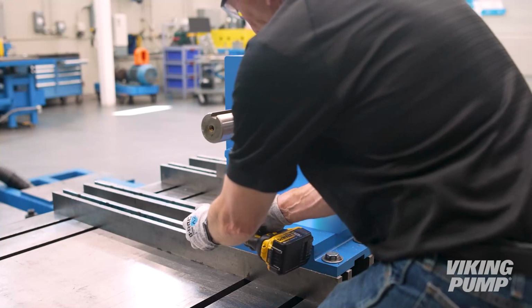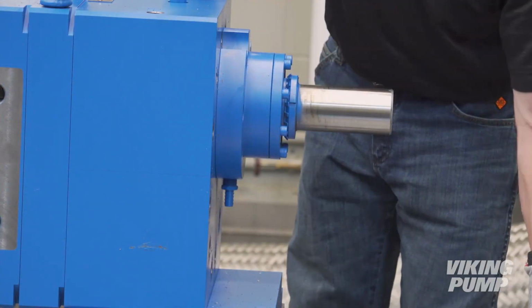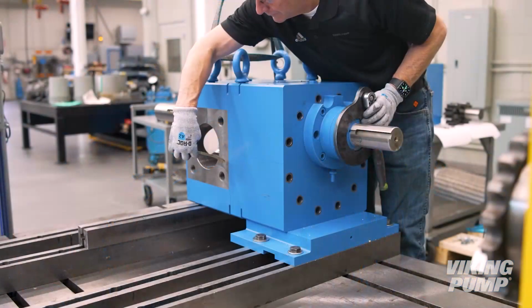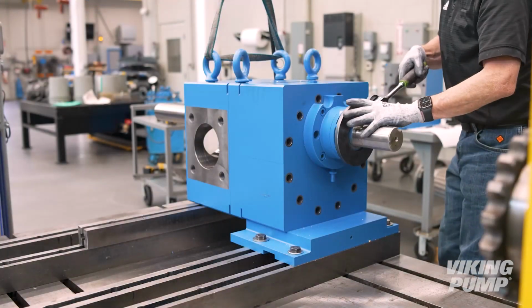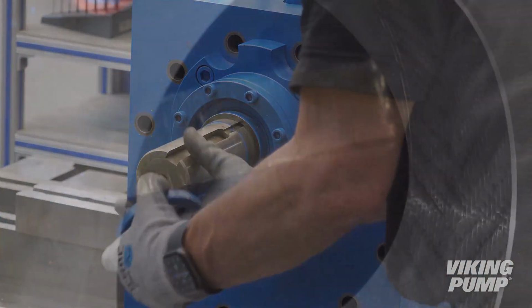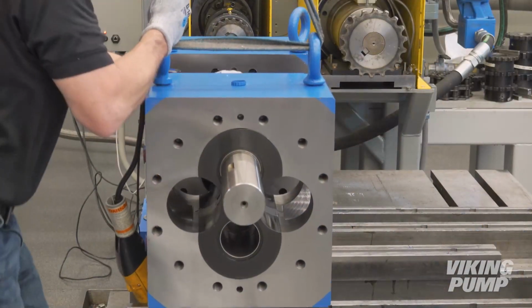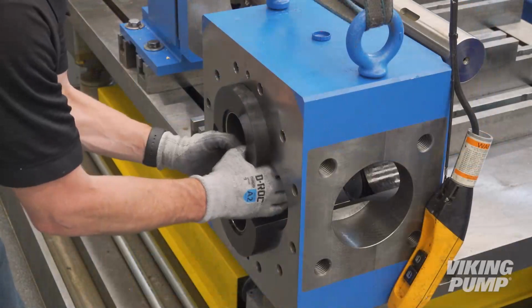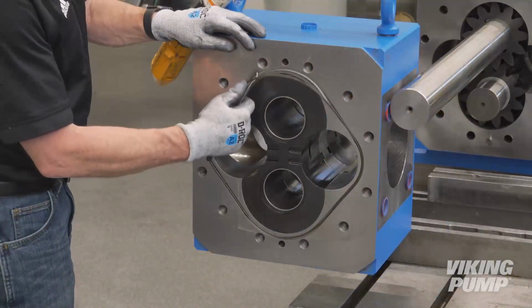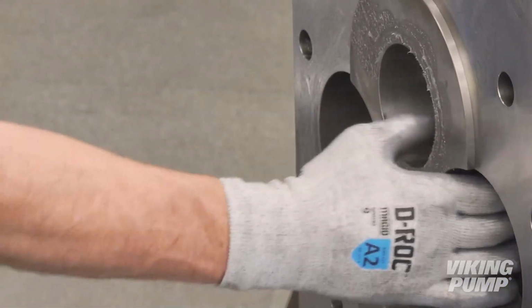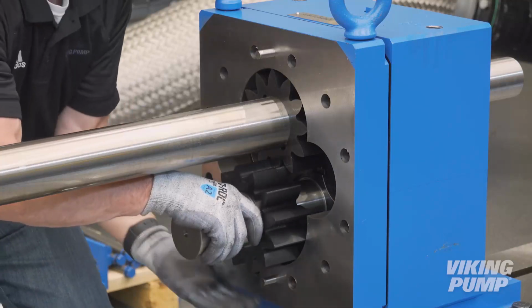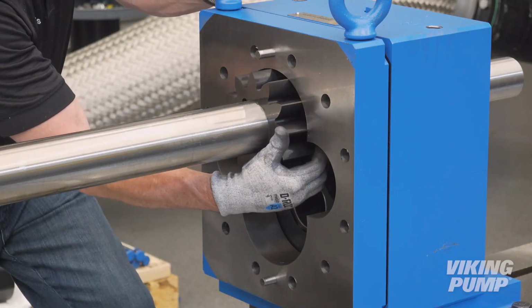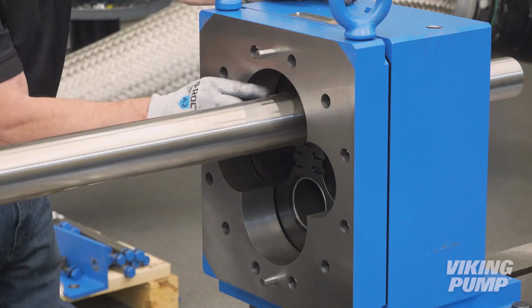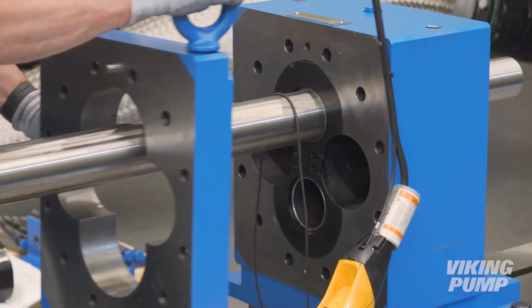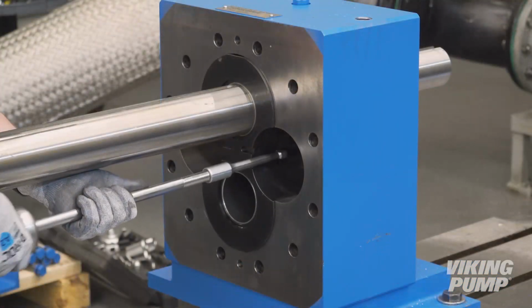Loosen and remove the cap screws on the bracket end of the pump. Discard these cap screws. Next, bend up the tang on the lock washer. Insert a brass bar or piece of hardwood through the port and between the gears to prevent the shaft from turning. Loosen and remove the lock nut and washer. Remove the brass bar. Next, remove the ported separation plate. Discard the two bushing blocks and gaskets and the O-ring. Retain the ported separation plate and the spacer for reassembly. Remove and discard the next driven gear, driven shaft, driver gear, and drive pin. Remove and discard the next alignment pins, casing, and O-ring. Remove and discard the final bushing block and gasket.